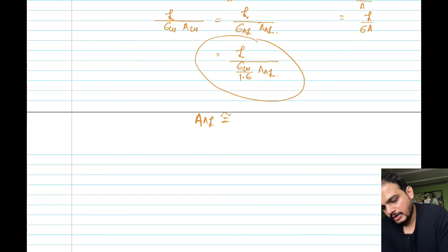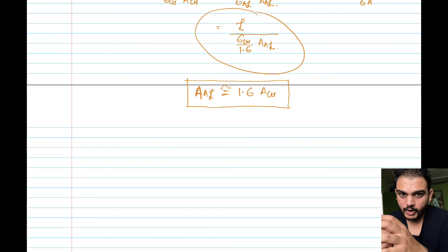So is this advantageous or disadvantageous? For the same operating voltages, if we go for aluminum conductor, we require more cross section area as compared to copper conductor. This is obviously advantageous from the point of view of occurrence of corona, because corona will be less if the cross section area is high. If the cross section area of the conductor is high, then on the surface of the conductor the gradient of electric field intensity will be less. And if the gradient is less, the chances of occurrence of corona will get reduced.